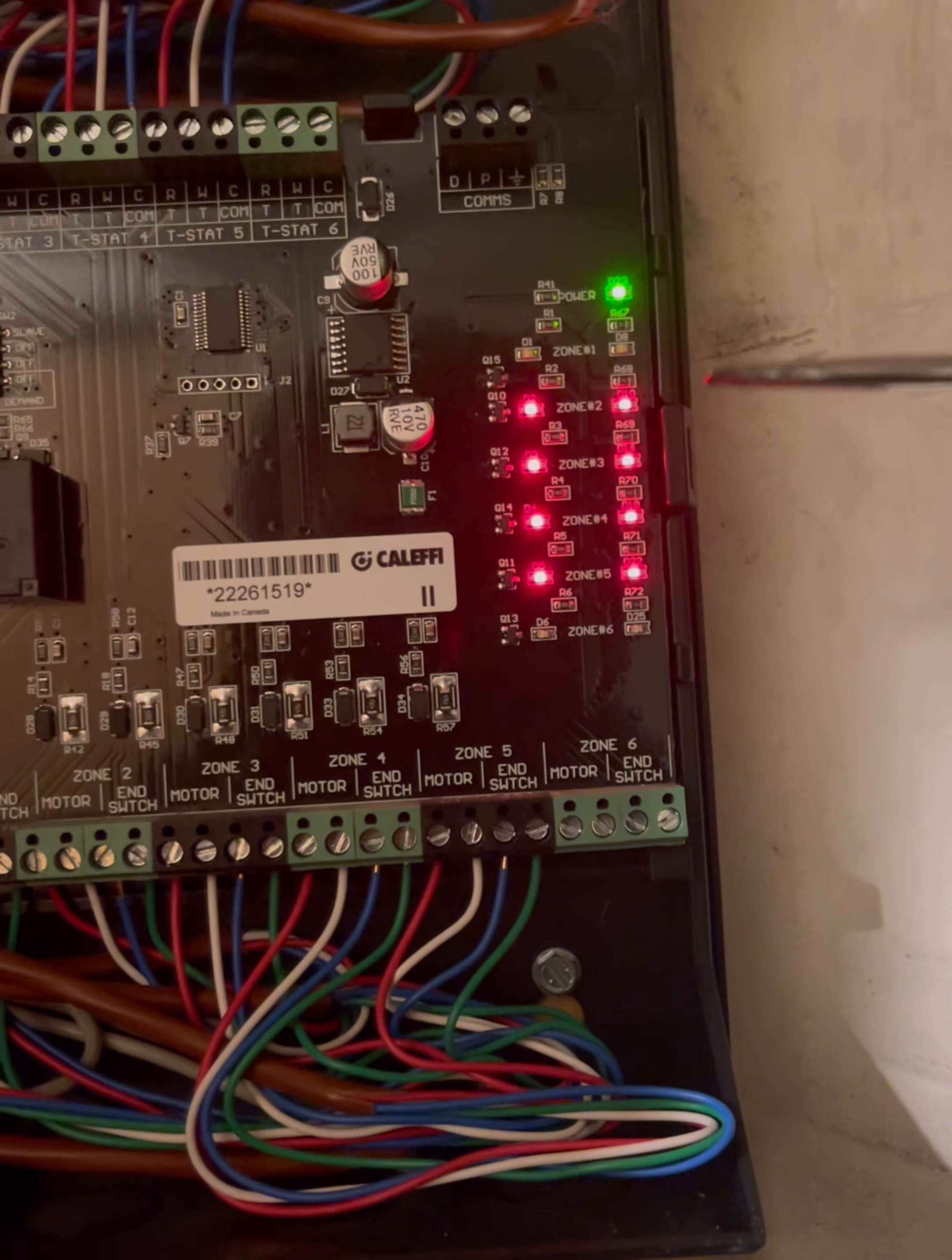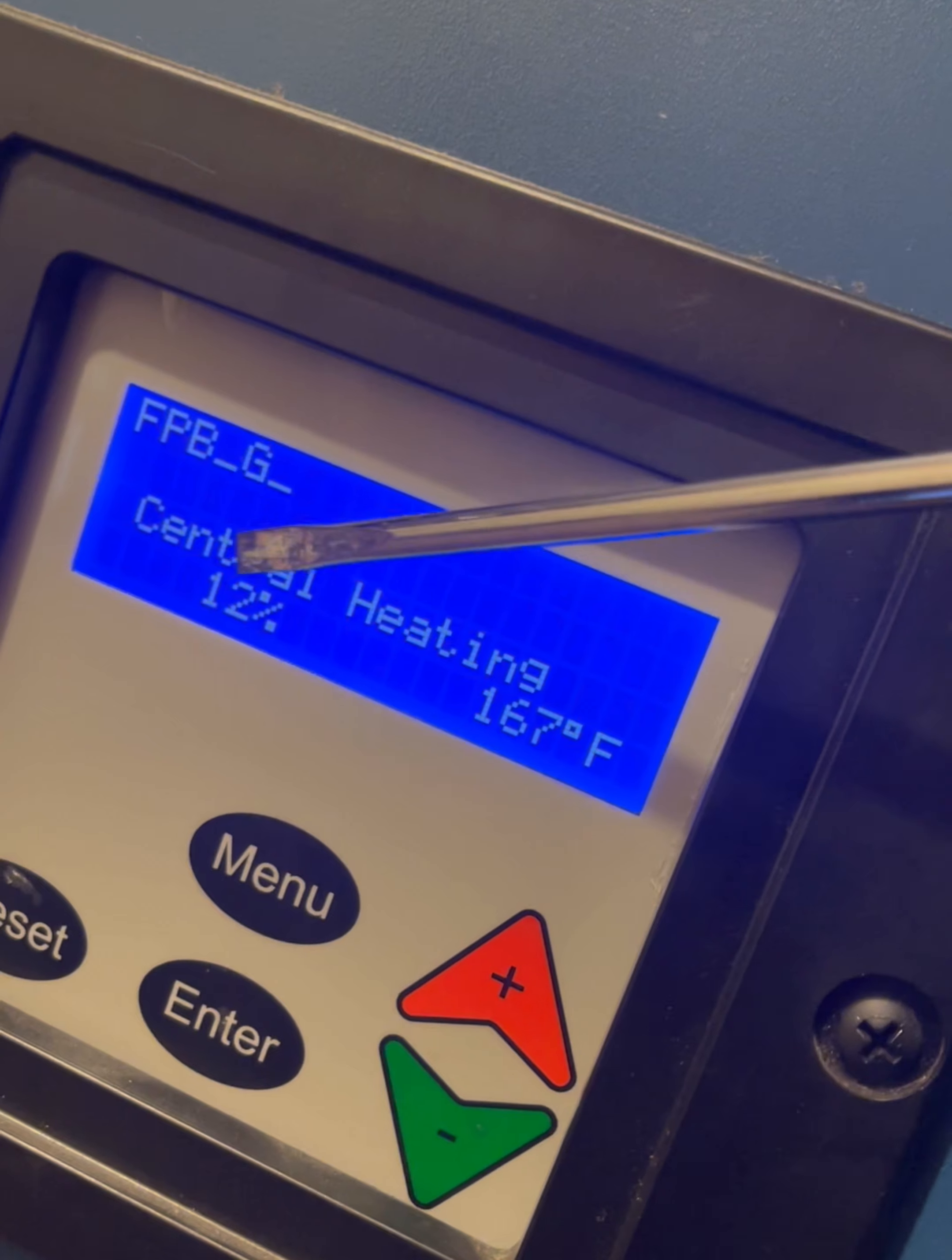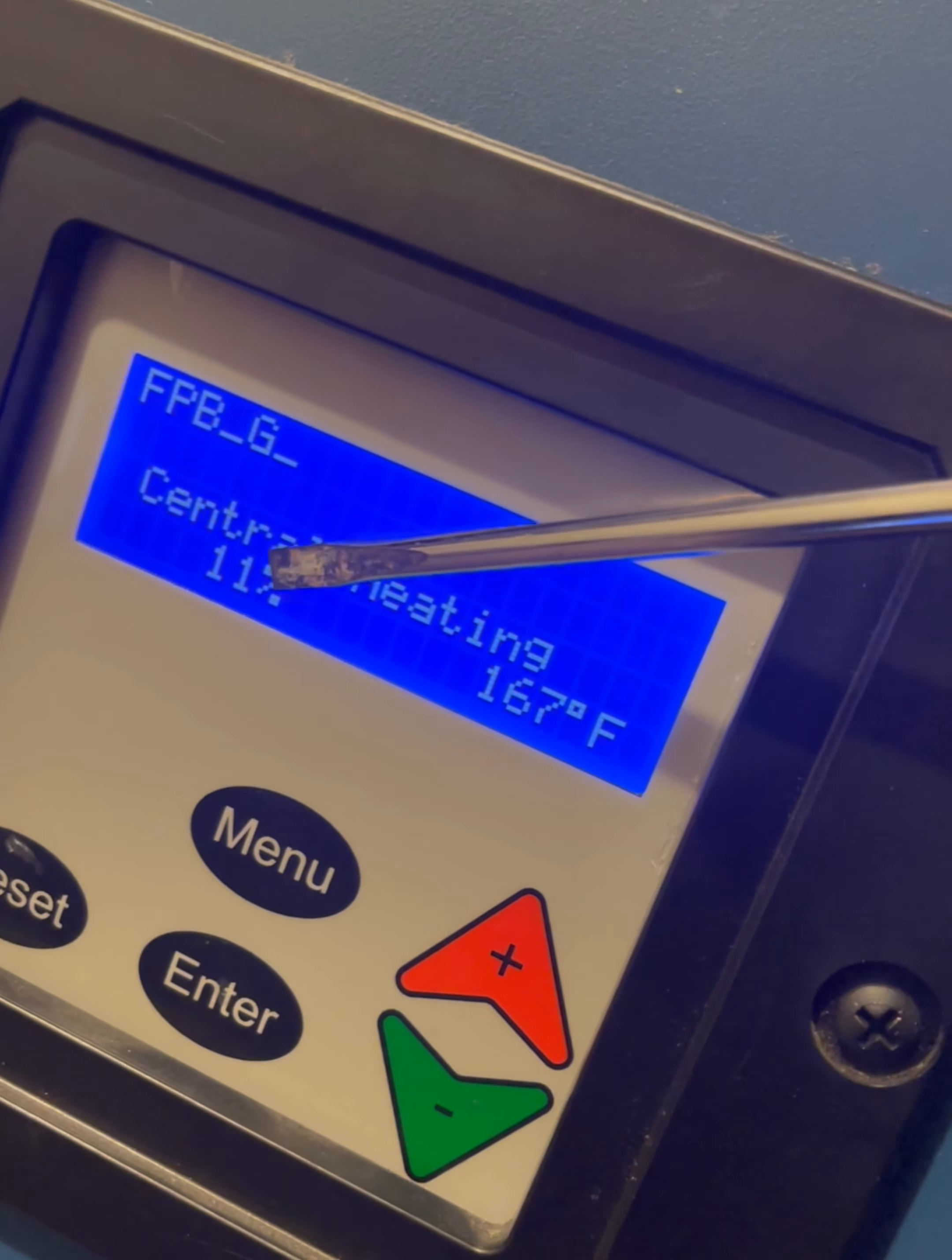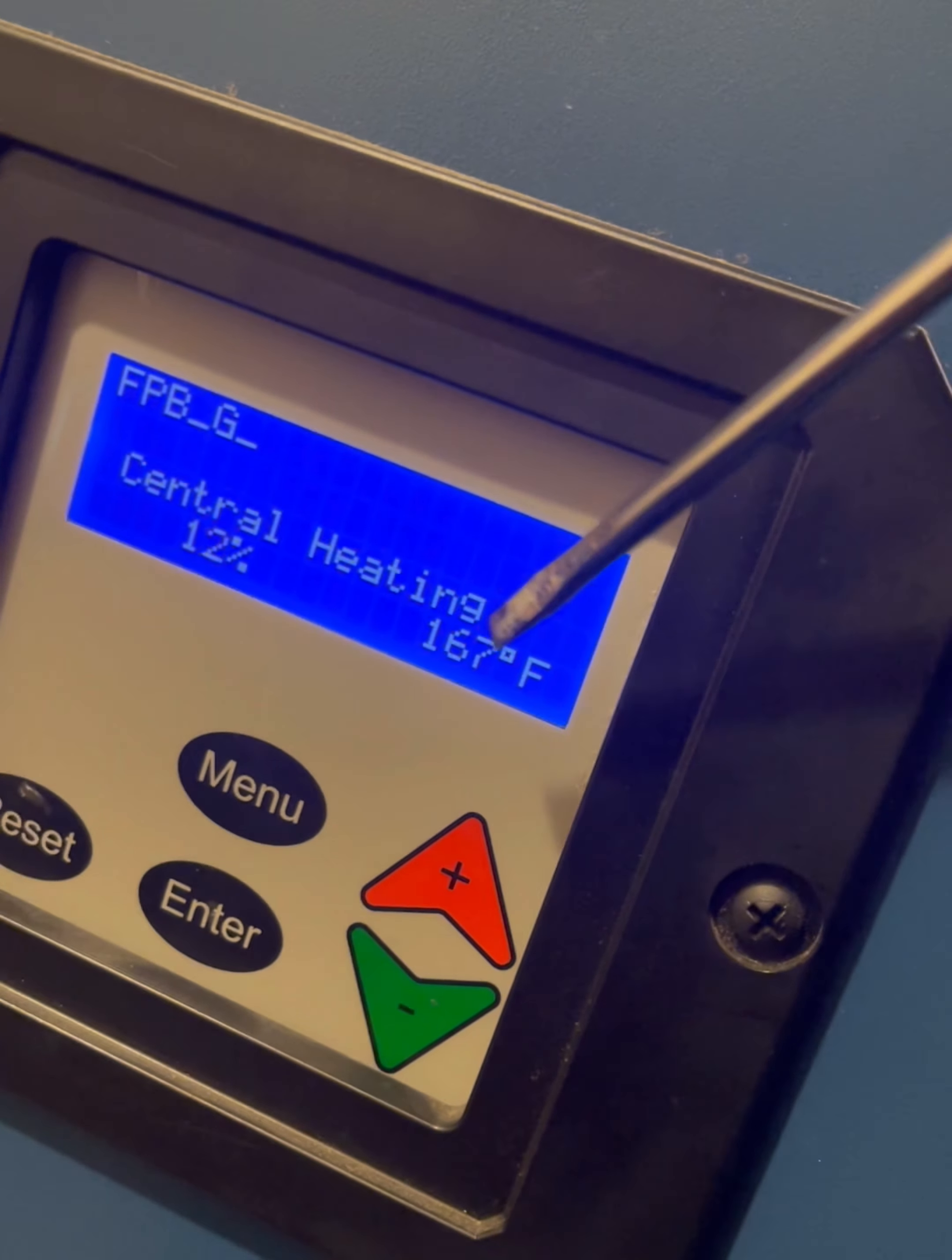So anyway, zone three, okay, I'm gonna go upstairs and turn the thermostat on and see what's going on. Okay, so you see how the system went on right away? She said she's 1E. Yeah, this has one and two. It's twelve percent. You see the percent sign? Twelve percent, oh eleven percent. And this is the water temperature, usually at 180 is where we're at. So we got the circulator pump, is it circulating? Oh it's down here.